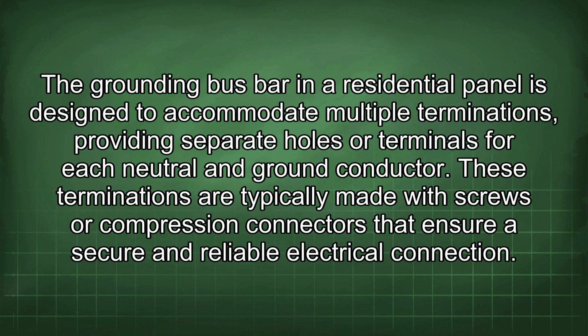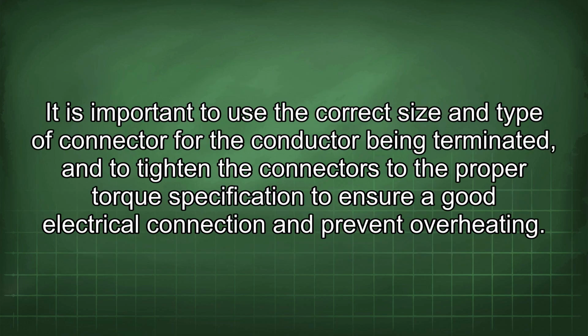The grounding bus bar in a residential panel is designed to accommodate multiple terminations, providing separate holes or terminals for each neutral and ground conductor. These terminations are typically made with screws or compression connectors that ensure a secure and reliable electrical connection. It is important to use the correct size and type of connector for the conductor being terminated and to tighten the connectors to the proper torque specification to ensure a good electrical connection and prevent overheating.